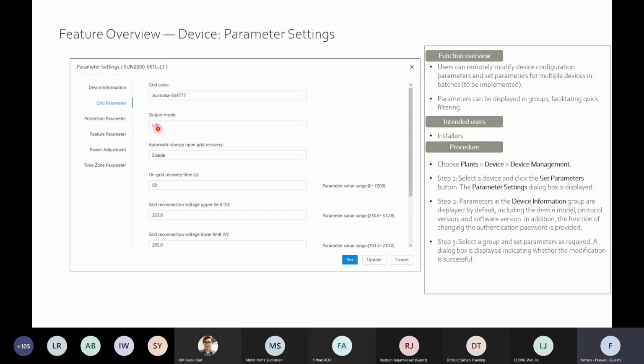Normally for protection, especially on factory sites, many customers ask about sudden alarms regarding over voltage or under voltage. Under voltage normally happens in Sabah and Sarawak, where villagers tapping the voltage cause your grid voltage to drop. For this, you can adjust the settings, but we just advise you on this — we don't teach you to ignore the regulations for protection. If over voltage normally happens, you can alter level 1 and level 2 over voltage settings to solve the alarm issue, because when this alarm happens, your inverter stops generating power and you lose yield.